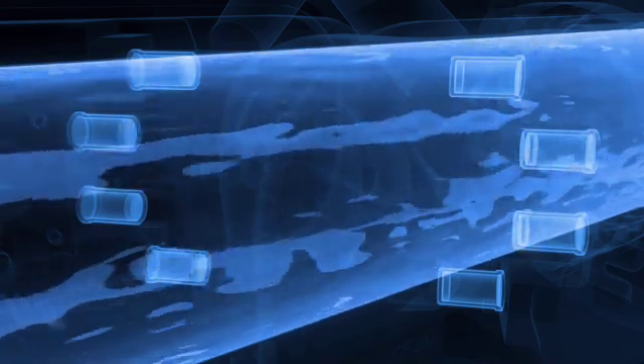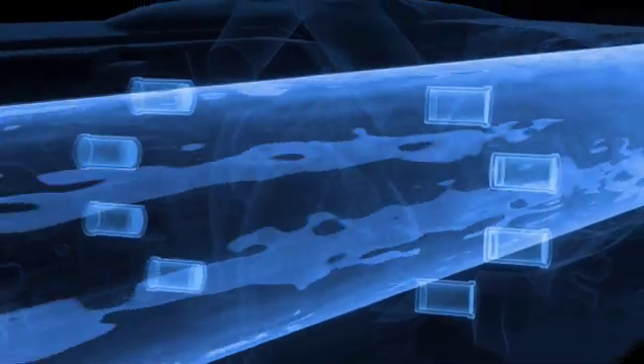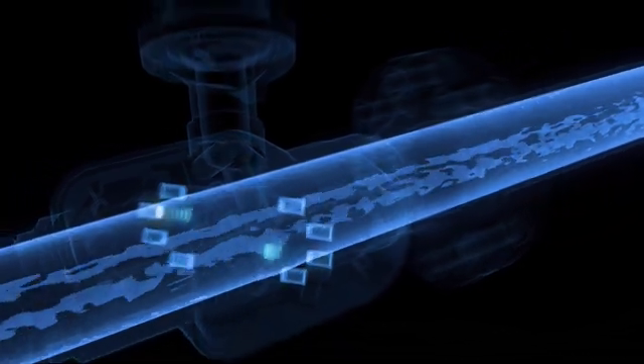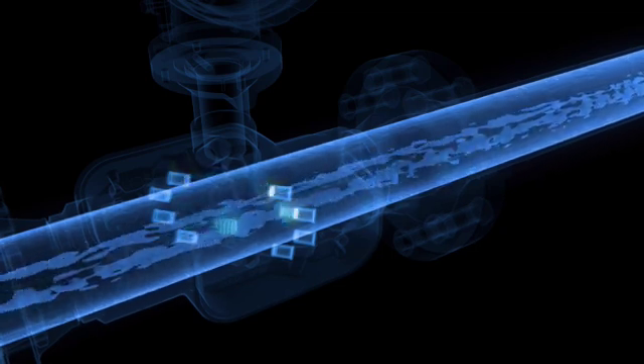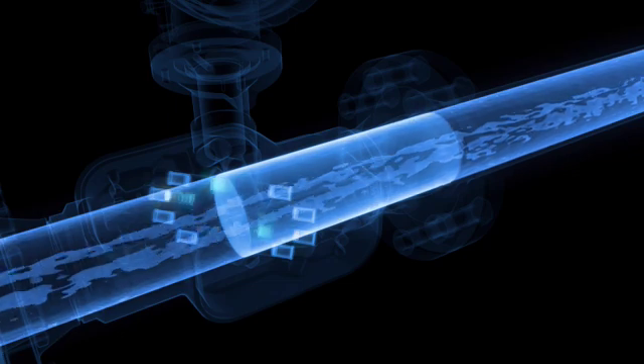Less time in the direction of flow and more time against the flow. Therefore, the differential transit time measured by the sensors is directly proportional to the flow velocity in the pipe. Together with the known tube cross section, the actual flow volume can then be calculated.